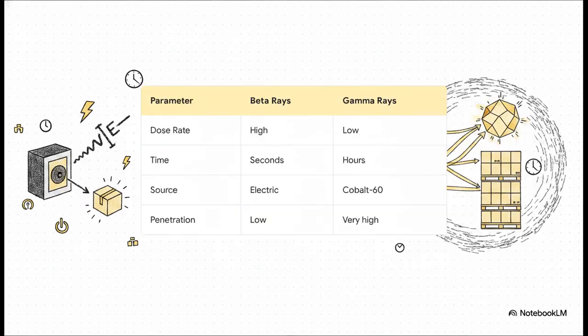There are two main types of radiation used for this, beta and gamma, and they operate very differently from one another. Beta rays, or E-beams, are actually generated using electric current and a particle accelerator. They deliver a massively high dose of radiation in mere seconds, which is awesome for the materials, but they have a pretty low penetration depth, so they really only work on individual boxes. Gamma rays, on the other hand, are emitted from a decaying radioactive isotope called cobalt-60. They have a much lower dose rate, meaning the product has to sit inside this heavy irradiation chamber for hours. But man, their penetration power is absolutely immense. You can sterilize entire, massive pallets of product all at once with gamma rays.